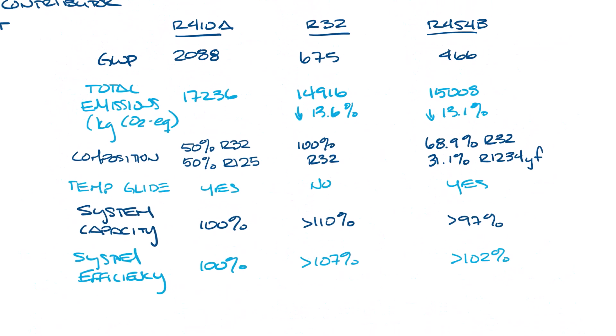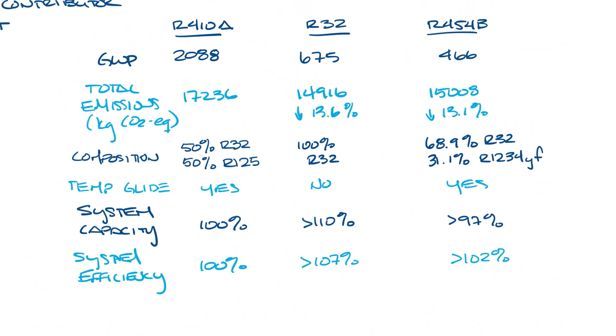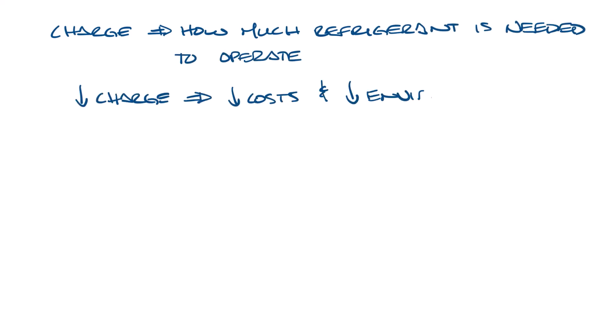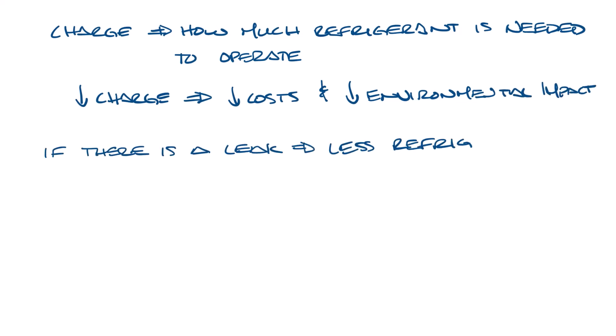And lastly, let's go back to the table and look at refrigerant charge. Again, R410A is the baseline, so I'm going to leave this blank. R32 has up to a 40% smaller refrigerant charge, and R454B has up to a 10% smaller refrigerant charge compared to R410A. Charge size refers to how much refrigerant the system needs to operate. Smaller charge sizes reduce both cost and environmental impact. And if there is ever a leak, less refrigerant means less refrigerant to leak and less potential greenhouse gas emissions.